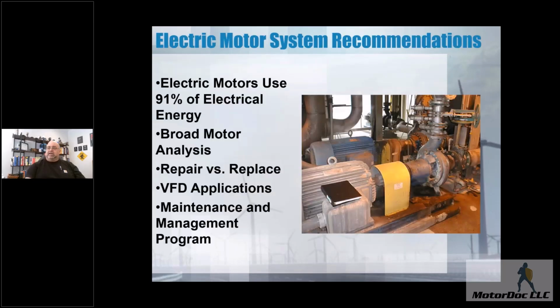That was that compressed air system. Back to this one, we did an overall motor survey of the facility. One of the big things we did that was good for the energy and reliability part is we made all the decisions on the motors ahead of time. What was available, what needed to be inventoried. 91% of their electrical consumption went through motors, so that was a big deal.